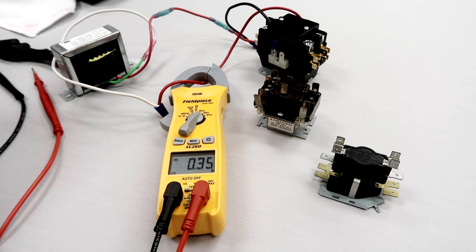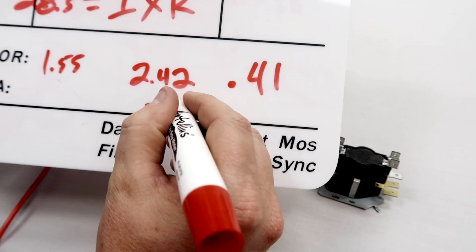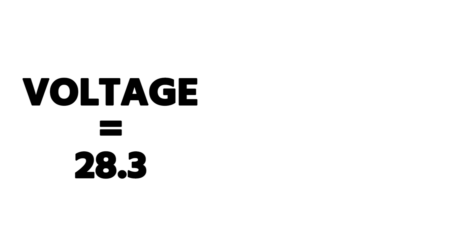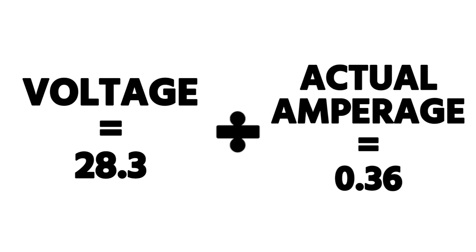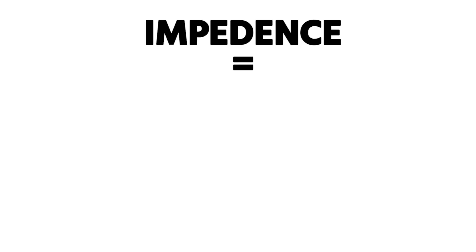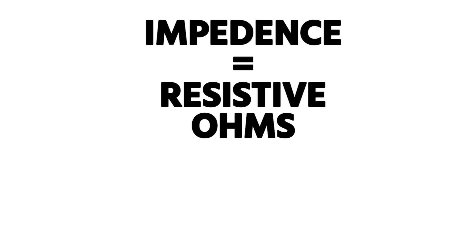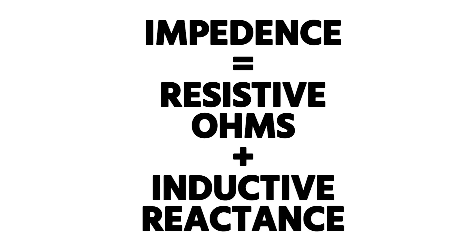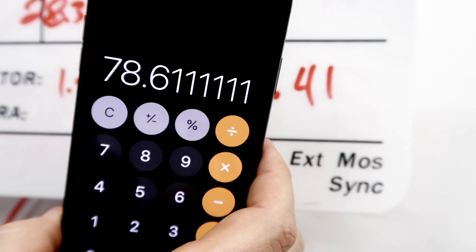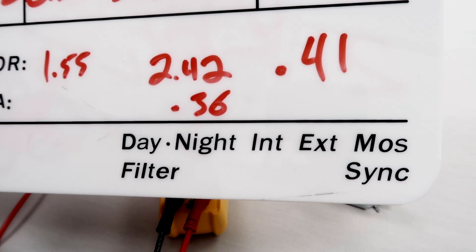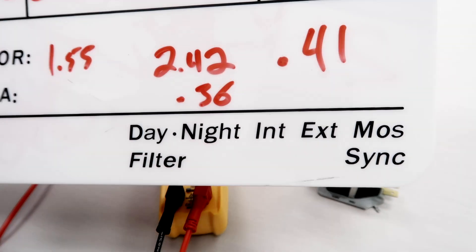I can actually tell you what the total circuit impedance is. If we know our voltage is 28.3 and our actual amperage is 0.36, then 28.3 divided by 0.36 gives us our true circuit ohms — and that would be the impedance. Impedance is the combination of resistive ohms you can measure with a meter while it's static, plus the inductive reactance that occurs within an electromagnet due to expanding and collapsing electrical fields. With an electromagnet you get this additional resistance that only shows up once you energize the load.